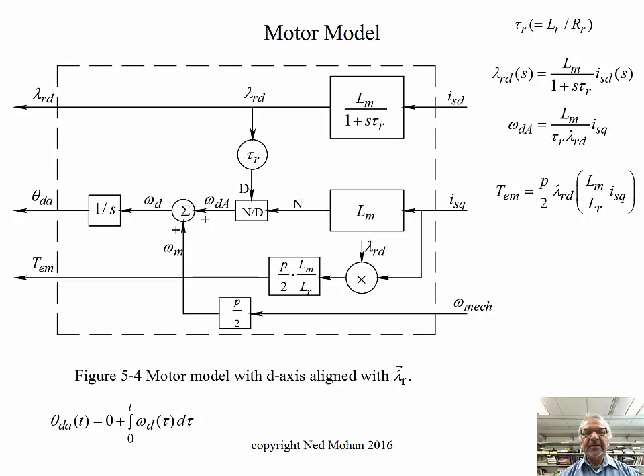And as you can see here, this calculation of where that d-axis is depends upon motor parameters, as they are shown over here. And particularly, this tau sub r depends upon the rotor resistance. And this rotor resistance is not always accurate to measure, but also it can change quite a bit as rotor heats up. So unless there is some estimation of how that rotor resistance is changing, we could be off quite a bit. So you can see all these things are dependent upon machine parameters here.